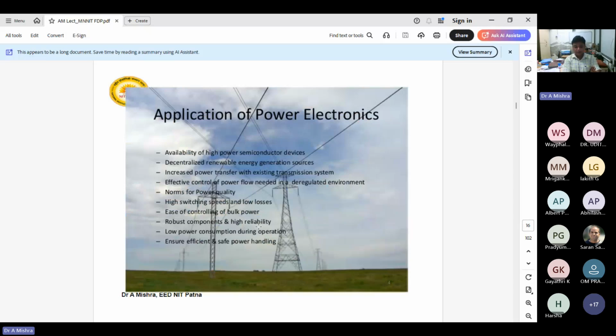You are aware that transmission is over longer distances. So what are the certain problems? Being a power system engineer, you must be able to relate to the compensation problem, the tower size problem, and how to deal with any fault. And on this much longer transmission line, there will be losses, and there will be maintenance of conductors, towers and all. So all these things become easier if you shift the whole AC transmission to DC transmission.